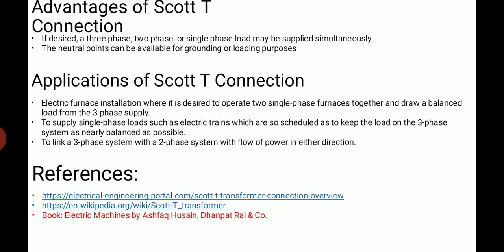The applications of Scott T connection are the electric furnace installation where it is desired to produce or to operate two single phase furnaces together and draw a balanced load from three phase supply. Second is to supply the single phase loads such as electric trains which are so scheduled as to keep the load on three phase system as nearly balanced as possible. And to link a three phase system with two phase system with flow of power in either direction, the Scott T connection is used.